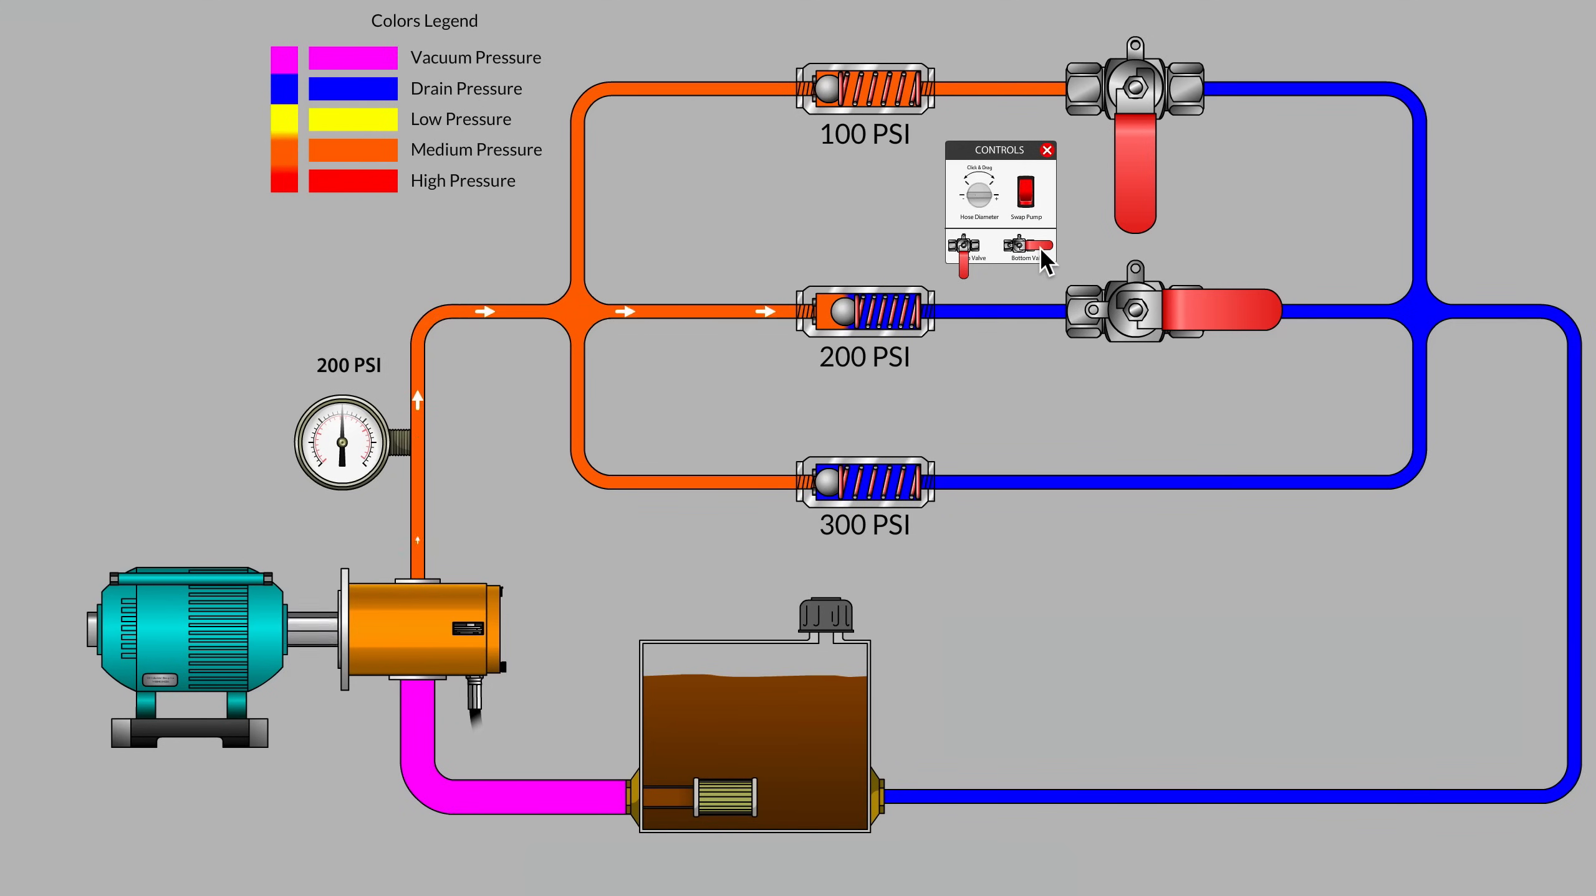Now if we close the bottom valve, it makes sense that the system pressure will rise all the way to 300 psi because that's our only remaining path for fluid in the hydraulic circuit. What happens if I leave the 200 psi path blocked and I open the shutoff valve on the top parallel branch? Quite correct. We go back to 100 psi as the top branch becomes our path of least resistance once again.